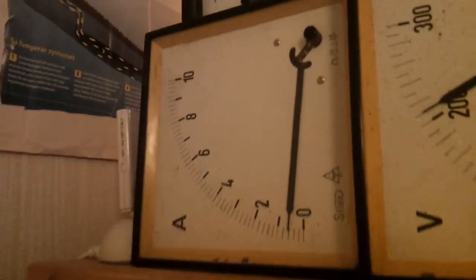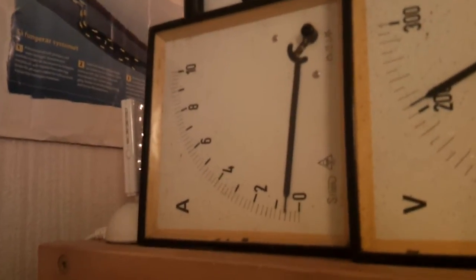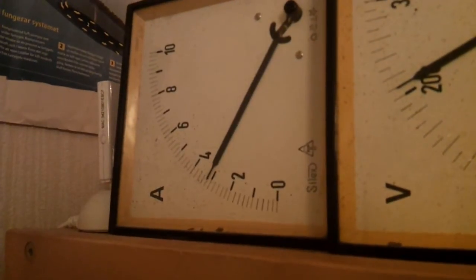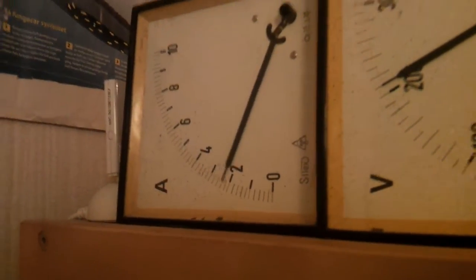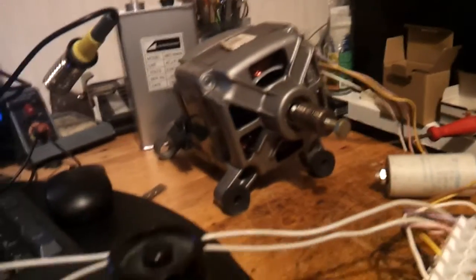And this is what happens if you put full power at the beginning. Peaks to 4 amps. But the soft starter only pulls 2.5 or 3 amps.